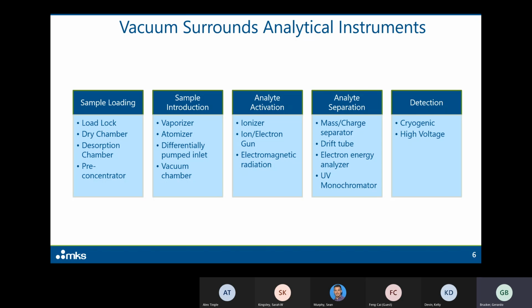Of course, that requires vacuum. I have to be able to go from atmosphere to high vacuum, and then be able to expose that chamber to an even bigger high vacuum system without an inrush of gas and so on. I also have to have a good differential pressure measurement relative to atmosphere. I need to know the pressure of the load lock chamber relative to ambient, to make sure that when I open up the load lock gate to ambient, I don't get a huge inrush of air into the chamber, which could bring all kinds of problems.